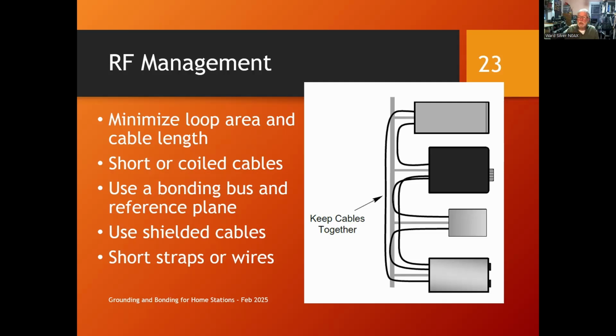Use a bonding bus like we just talked about, or a reference plane. I'll show you an instance of that in a minute. Always use shielded cables so that if you do pick stuff up, and you will, then the current that's flowing on the outside of the shielded cable, not the inside, the outside, will go to a grounded enclosure, and then it will be bonded together with everything else. By bonding stuff together, you minimize that current, and what current there is does not cause voltage differences. Short straps or wires for all of these connections is also important.